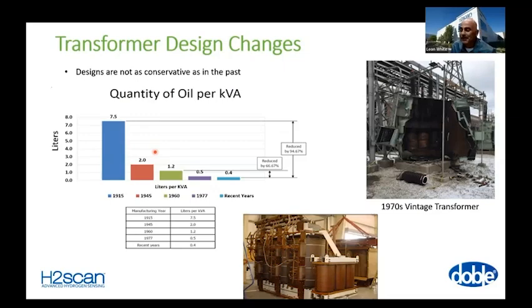I spent 10 years in substation design, and when I was buying transformers in the 90s and replacing failed transformers at the utility, most of the new transformers were roughly half the size for the same rating as the transformer being replaced. So we really didn't have an issue — the foundation was just fine to hold a transformer half the size, and we never had to enlarge the foundation as long as we weren't significantly increasing the rating.